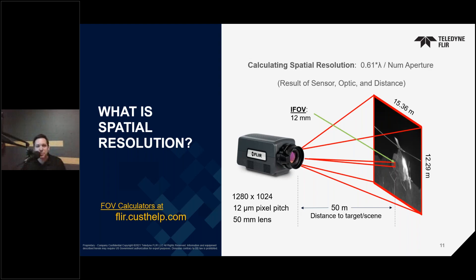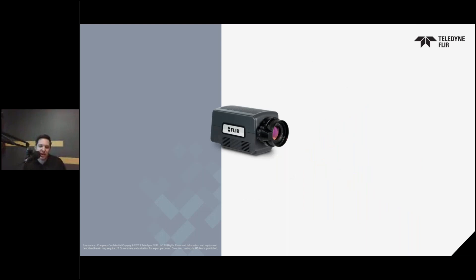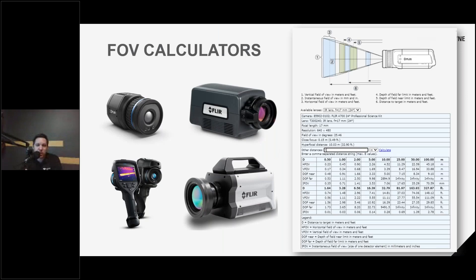I'd like to briefly show our field of view calculators. These are located in the FLIR Technical Support Center website at flir.custhelp.com and are provided for every commercially available camera we currently sell. You simply select the camera, then select the specific lens from a pull-down, enter the expected working distance, click calculate, and you get your results. The tool outputs a table of the resulting horizontal and vertical field of views, along with the IFOV or spatial resolution at the given distance in both imperial and metric units.